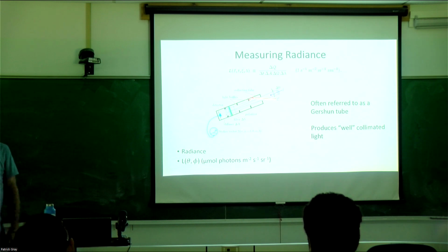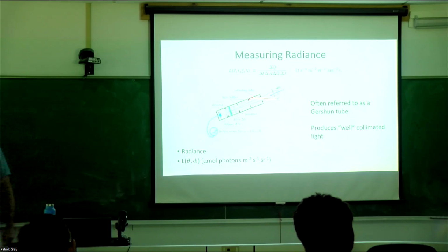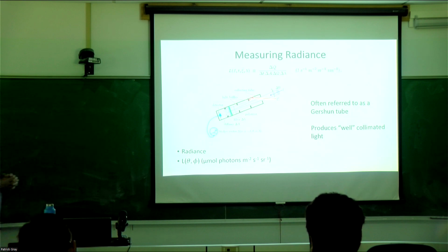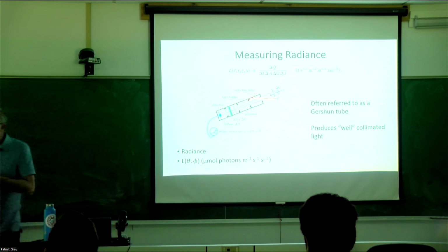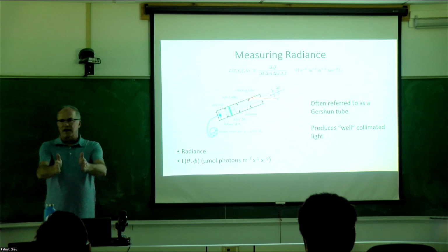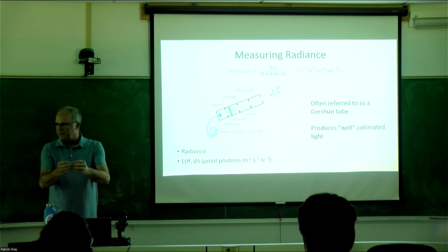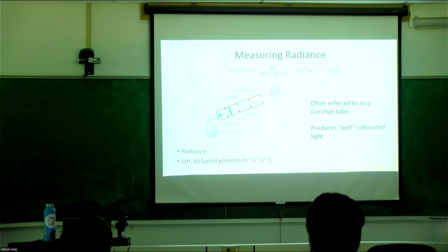In between the diffuser and the detector, the diffuser is not doing any focusing onto the detector. Is it just equally dispersing the light within that section? Correct. We're just trying to get rid of any variations in the light hitting that detector, so that if there's any spatial sensitivity of the actual detector, we're not pointing different light, and we're watching just basically a little beam steering on that. So we diffuse it slightly just to make sure it hits that detector. It doesn't really have a radial distribution in that small cone of light that we're detecting.